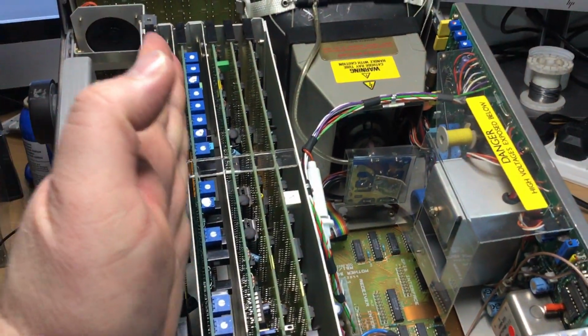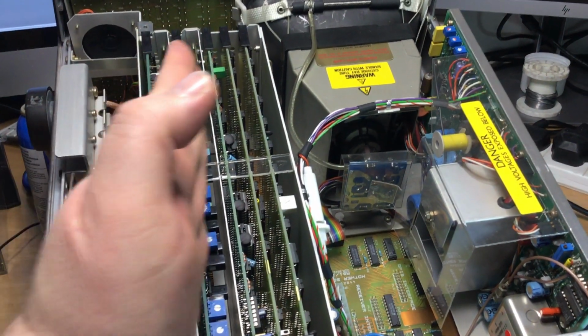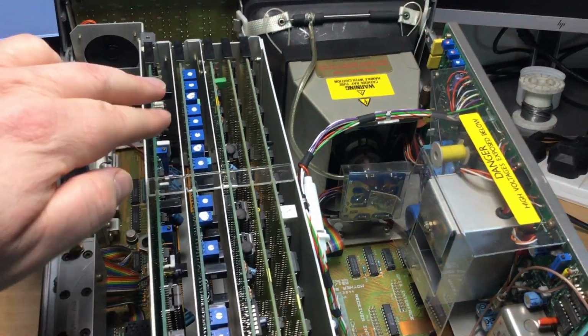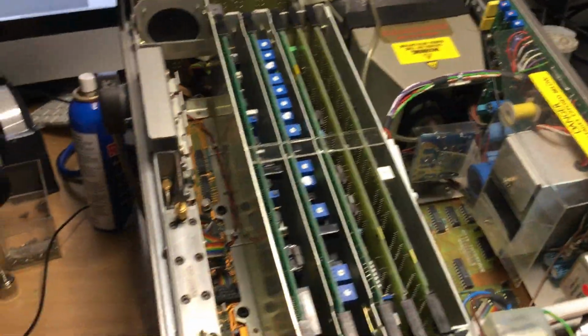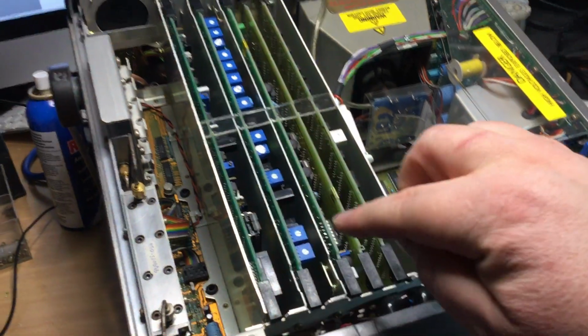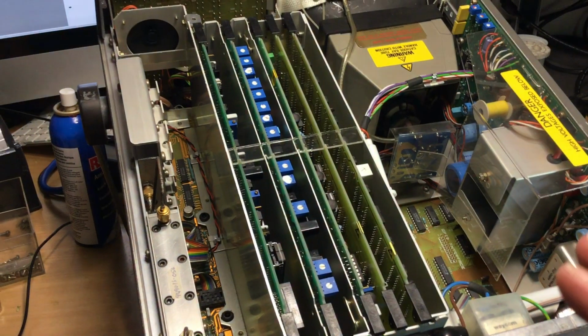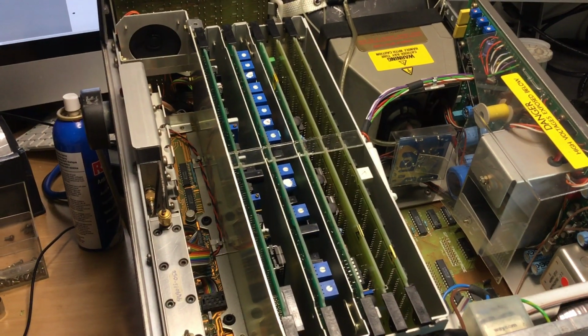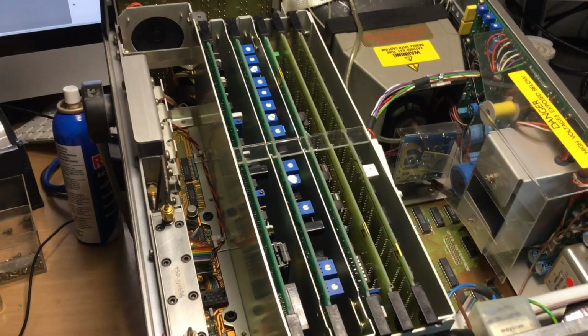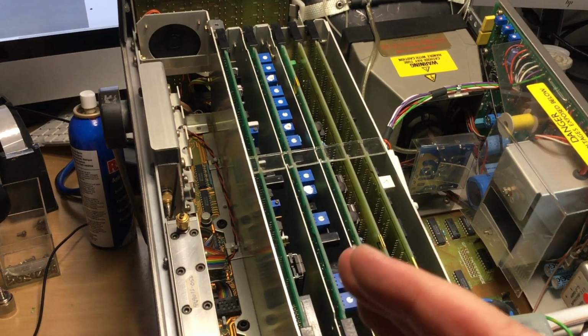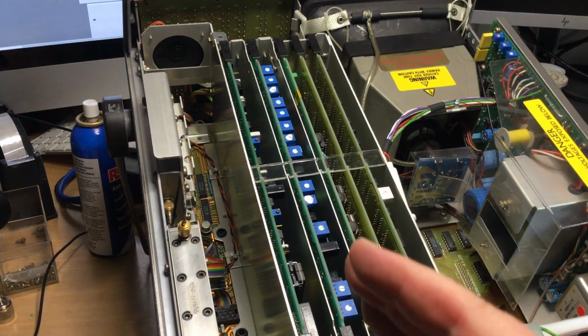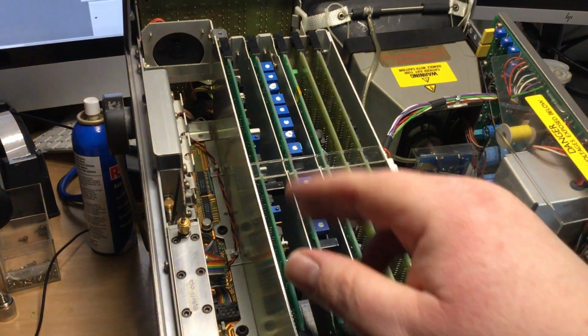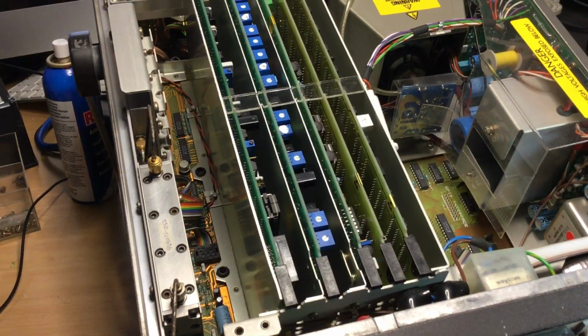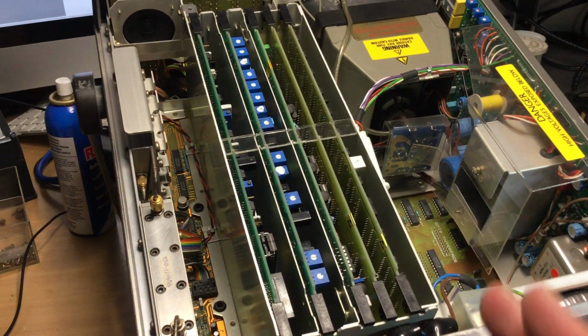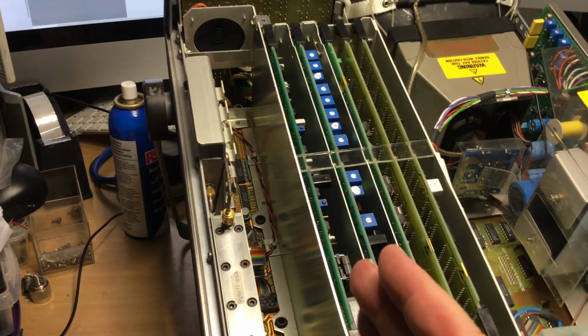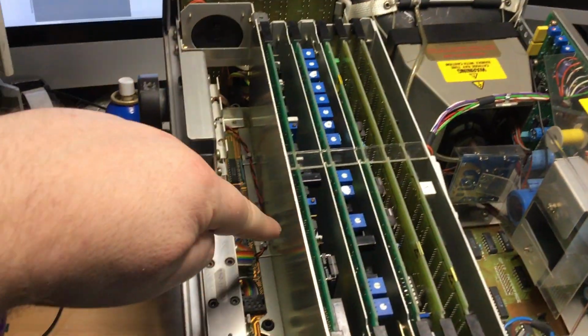These are the main boards which do some of the measuring of signals, as in modulation. The calibration is sort of 50-50 on these test sets. We have potentiometers which set up all kinds of different things from AF level outputs and inputs, the scope, the oscilloscope trigger points, and the general audio configuration side of a test set, TX power frequency, modulation depth, modulation deviation, all that can be set on these potentiometers, which is in depth in the service manual of how to do that. So basically, starting from the left is AB6 board, which is this board here.